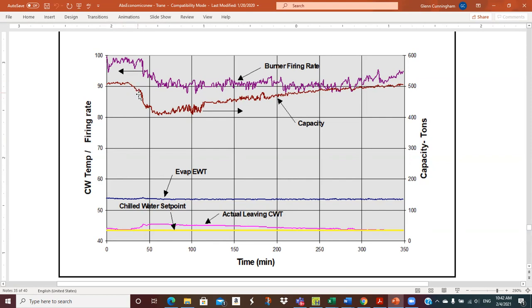We put all the air in the machine, and so what happens? That affects capacity. Capacity starts dropping. Now with the old controls, what would have happened is the controls would have sensed capacity dropping and it would have fired harder, which would have pushed us into a crystallization problem. But so they're bragging here about their controls. Look, the firing rate actually went down as the capacity went down because the controls realized that we have a leak. Okay, and so they don't want to crystallize, so they back off on the firing rate.